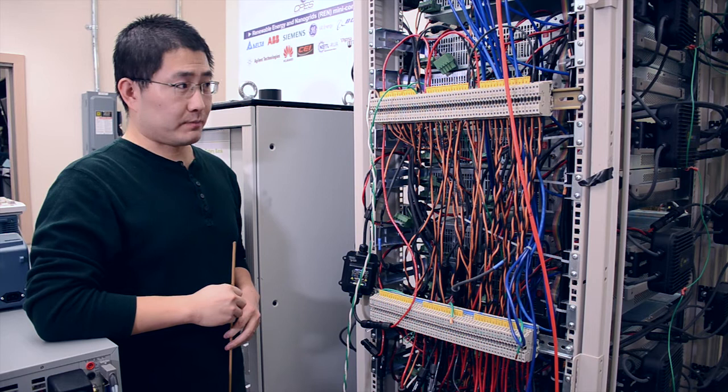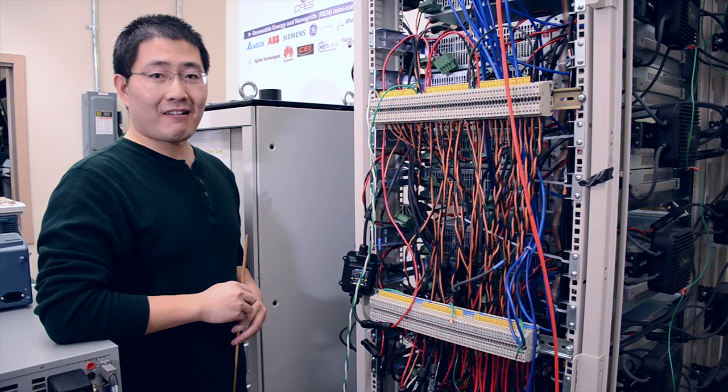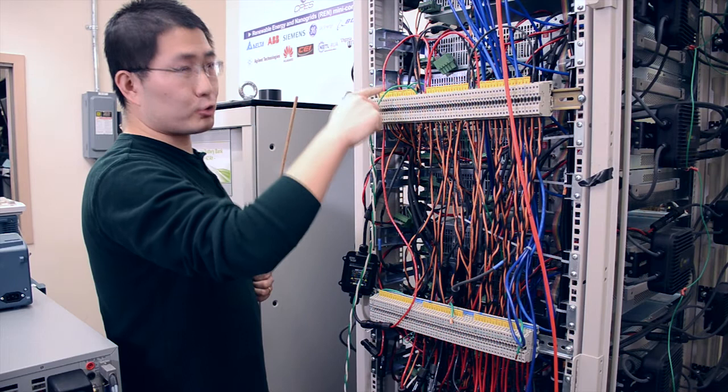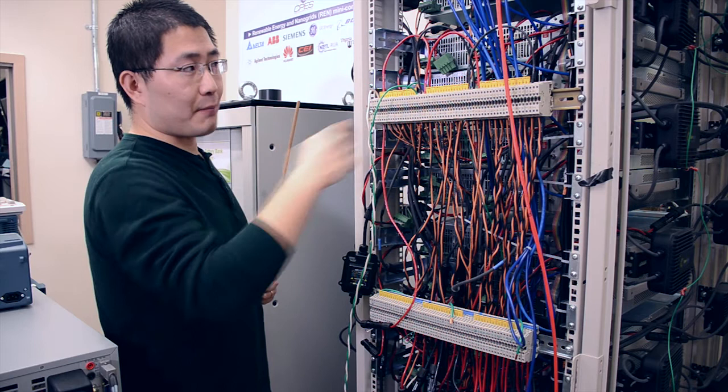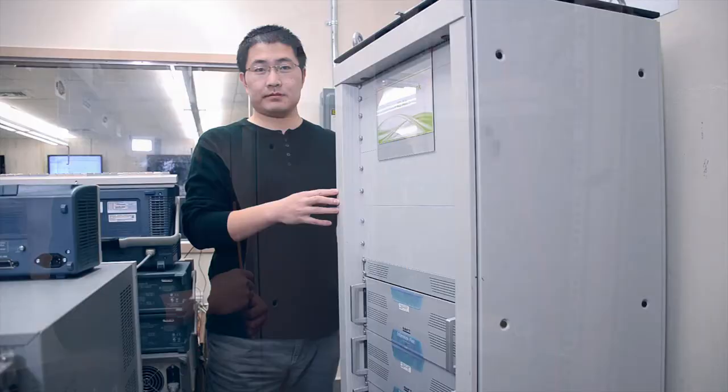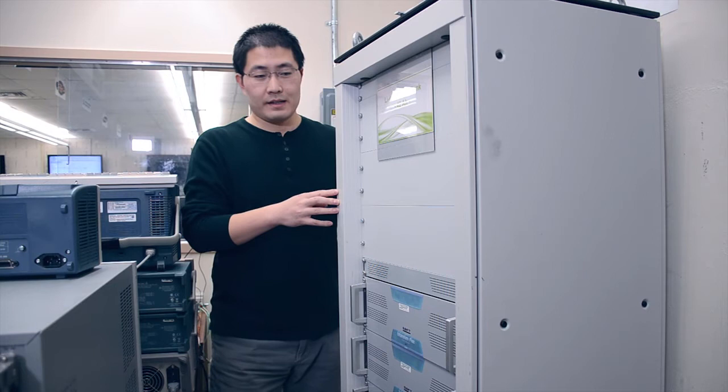To install all the 30 panels into the DC bus system, a DIN rail connector is used to easily configure the parallel and series connections. For example, in our system here, we have three strings. Every string has 10 panels in series connected, and the three strings are paralleled through the connections, the red and black wires.